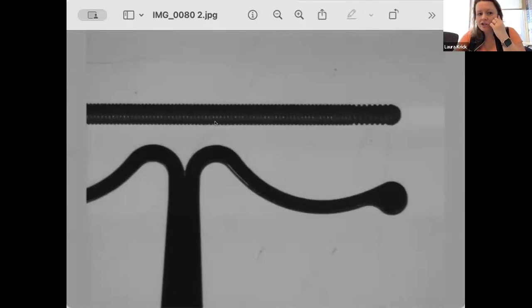So I wanted to just show the device in magnification. So this is, above it, a nitinol guide wire out of a standard PICC tray, the most common brand that was available. You can see the edges of that nitinol wire compared to the edges of the SecurAcath feet. From the ball to the ball on either side of the feet is 1 centimeter, the thickness is 1 millimeter, and they're 1 centimeter long. And you can see this curvature is designed with perfect intent to be able to reside under the subcutaneous tissue without a lot of friction and without a lot of concern for damage to the catheter.